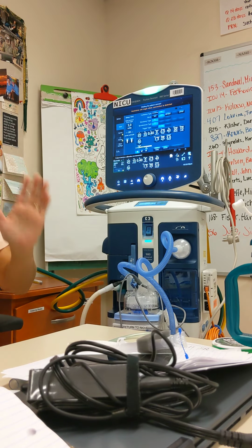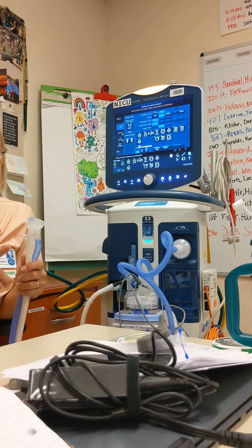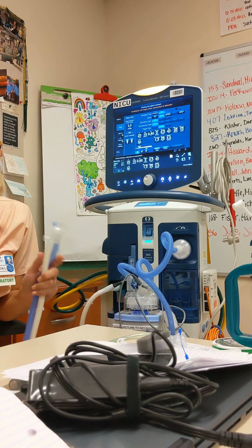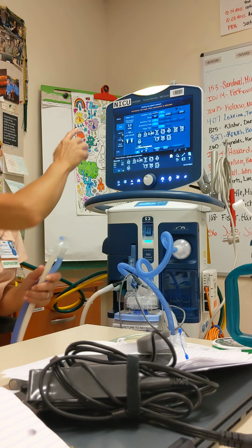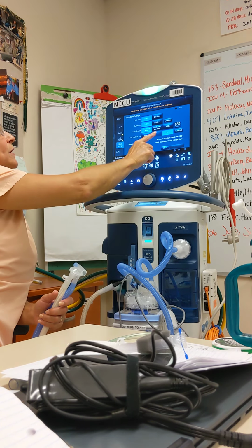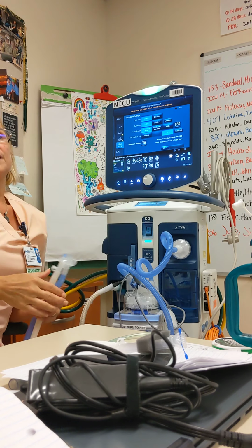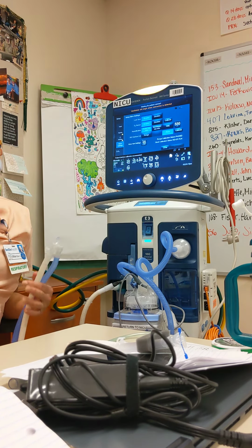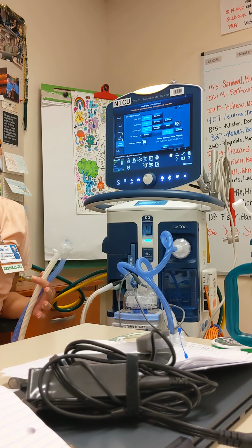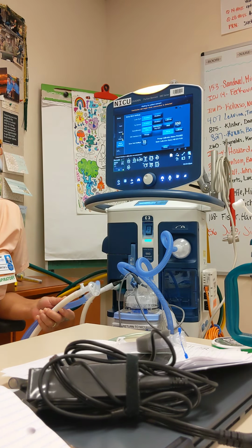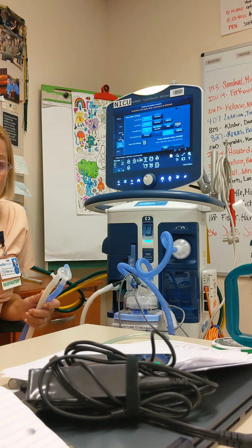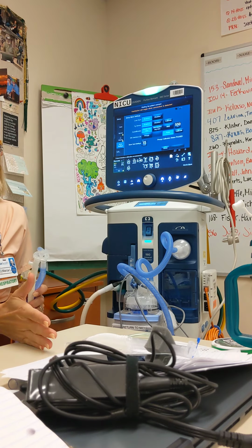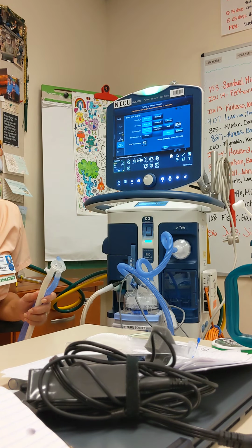If you think for any reason that they might want to use both, calibrate both right away. Take the extra 2 minutes to calibrate both. Because then when you're switching from one to the other, all you have to do is toggle between, this would say mask and prong then. This is going to be a trial and error kind of thing, and I'd be willing to bet the first time this happens, we're not going to know the baby was doing poorly and now we want to go to actual CPAP. But if you do happen to know that, take the time to calibrate them both so that you don't have to do it later when you're switching.